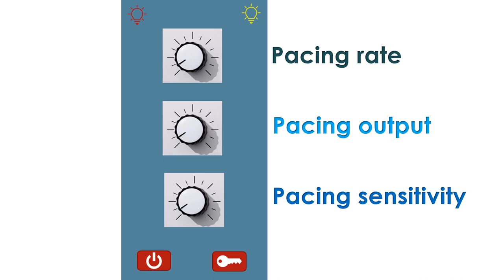Sensing is the capacity of the pacemaker to sense the natural signals from the heart if present, and wait. If a natural signal is not sensed, the pacemaker gives a pacing electrical signal at the end of the programmed interval. Sensing prevents competition between the natural signals of the heart and the artificial signals of the pacemaker, which may cause serious heart rhythm abnormality.